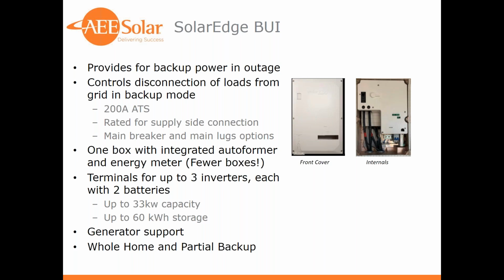Big part of the value prop on this BUI, or in this buoy, is one box. It's got an integrated auto transformer and energy meter. Another part of the feedback from customers was, hey, this solution's great, but by the time I get everything installed with conduit and a gutter and a backup panel, it looks like a yard sale on the homeowner's wall. You've got one or two batteries that cannot be stacked depth-wise, so they have to be stacked next to each other or on top of each other. So one or two batteries, a backup panel, a meter, an auto transformer, an inverter. It just gets to be a lot. So SolarEdge did the smart thing here and integrated those two components into the backup interface. Less clutter, easier install experience.